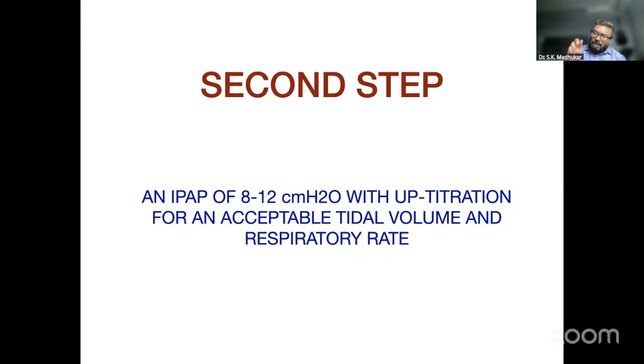And the target respiratory rate should be 12 to 16 breaths per minute. So you keep on increasing the IPAP till these two targets are met. And as I told you, the maximum IPAP that you can go is 30 centimeter H2O. And I'm telling you, don't be afraid of increasing the IPAP, because high intensity NIV, where IPAP goes up to 28, 29, has been found to be very successful in treating most acute hypercapnic respiratory failure.